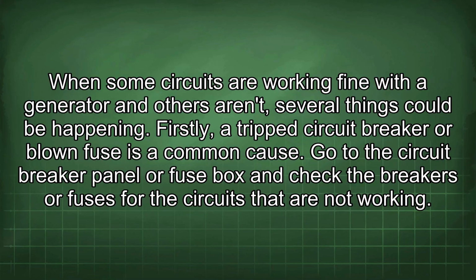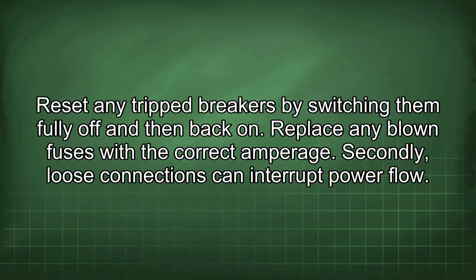When some circuits are working fine with the generator and others aren't, several things could be happening. Firstly, a tripped circuit breaker or blown fuse is a common cause. Go to the circuit breaker panel or fuse box and check the breakers or fuses for the circuits that are not working. Reset any tripped breakers by switching them fully off and then back on. Replace any blown fuses with the correct amperage.